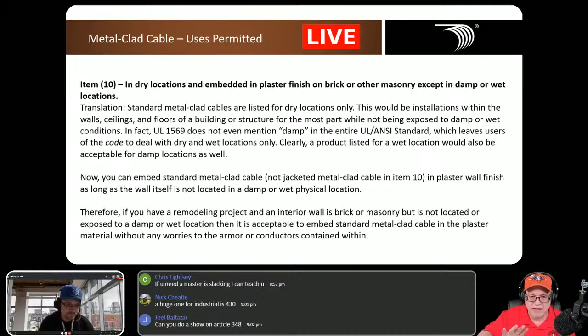All right, item number 11. Now, this is where we get to wet locations, Jay. What makes an MC able to now be used in a wet location? Yeah, it's going to be where a corrosive resistant jacket is provided over the metallic covering and any of the following conditions are met. And you have A, B, and C. Mm-hmm. So we usually will put the PVC material over the metallic covering. Right? Oh, yeah. So that meets the first item, that PVC MC that you were talking about that I could use outside. So look at the next three, A, B, and C.